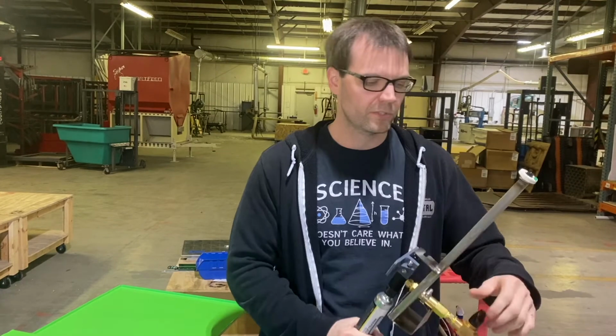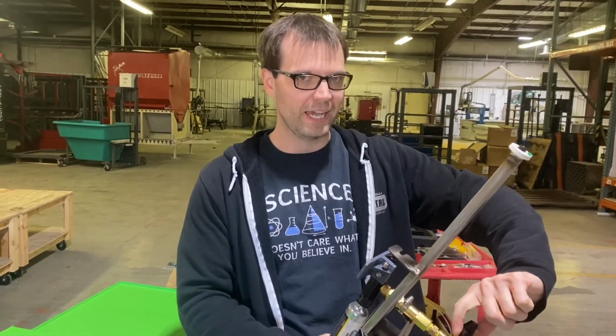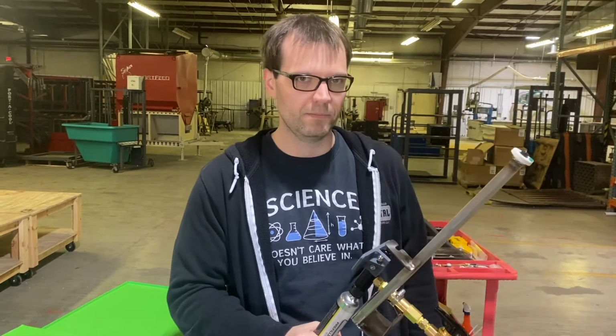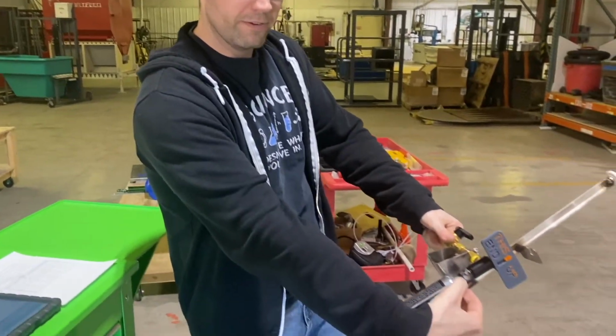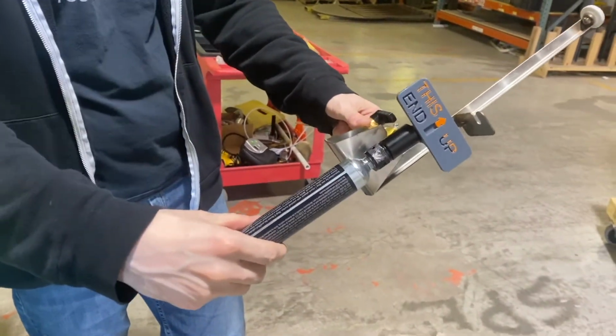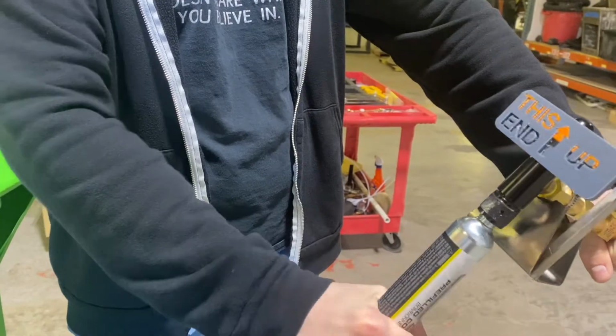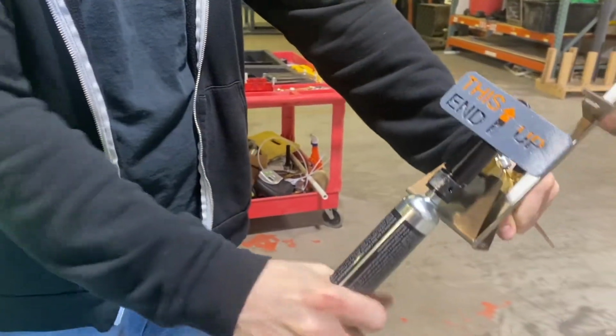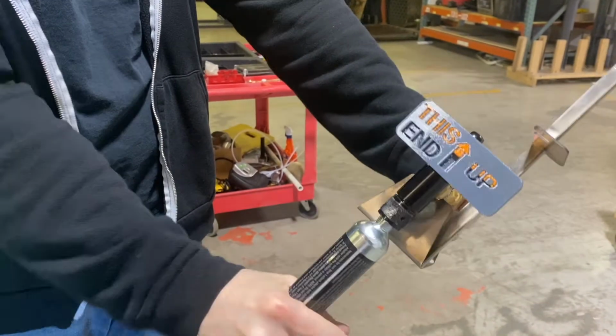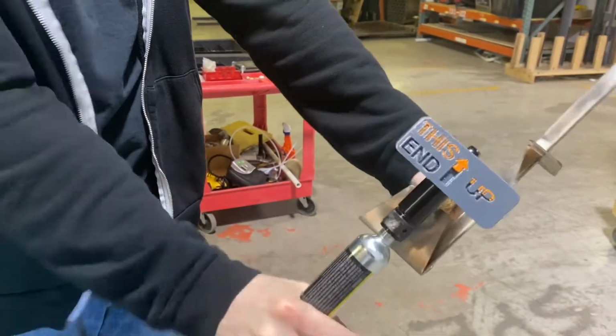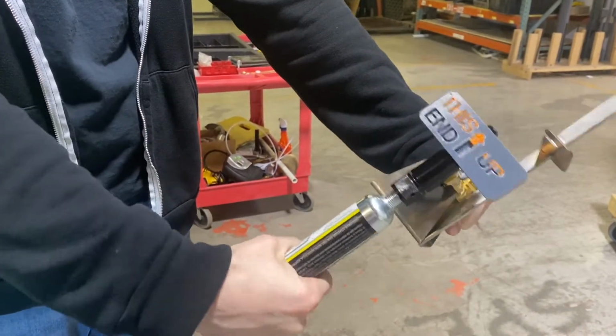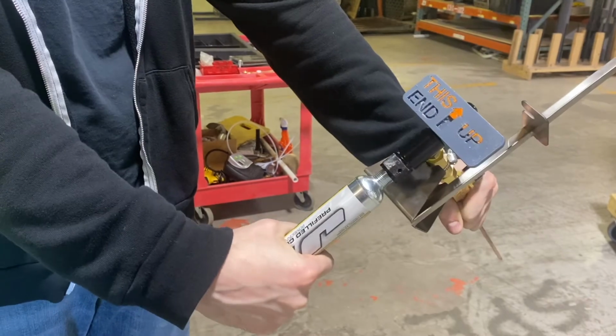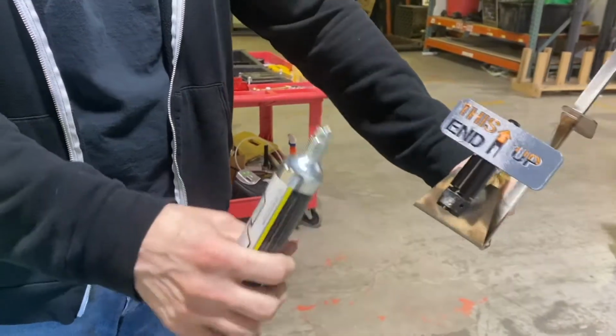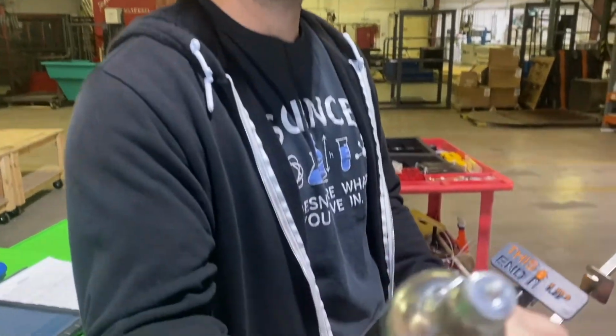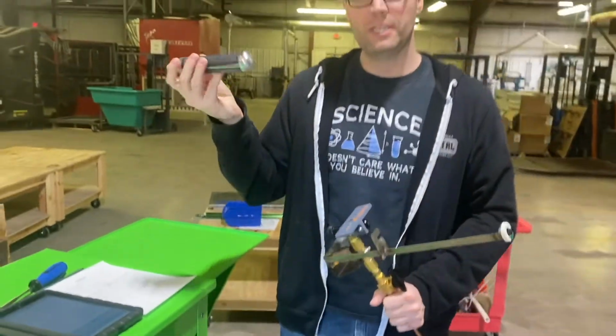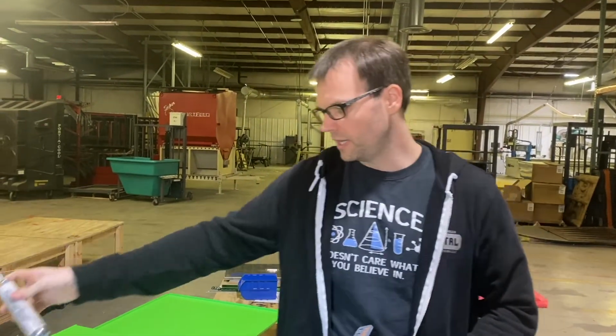So just like I was careful when I installed the cartridge, I'm going to be just as careful when I'm removing it. So what I usually like to do is actually start releasing the gas, not anywhere near the system, but just start releasing it. And then I'm going to keep my hands far away from this area right here, because that's where all the gas is going to vent out of. So I'm going to keep it upright and just turn to open it. All right, so in fact you can see some dry ice form right there. So this is just an empty cartridge. You can recycle this and dispose of it as you want.